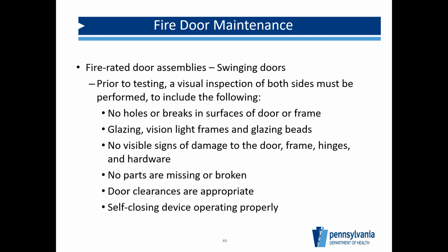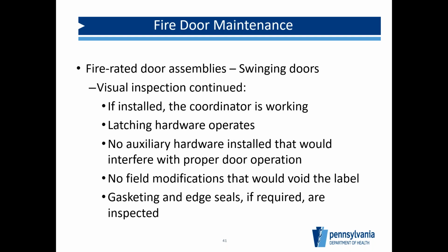Those gauges are helpful and available online. As for self-closing hardware, something important to note is that fire doors are labeled by the manufacturer, and there can be no field modifications that would void that label. So if we decide to screw in a large metal kick plate on the bottom, that likely voids the label on the door. We can't make those kinds of changes in the field unless it's done by someone from the manufacturer or approved by the manufacturer to make those changes.